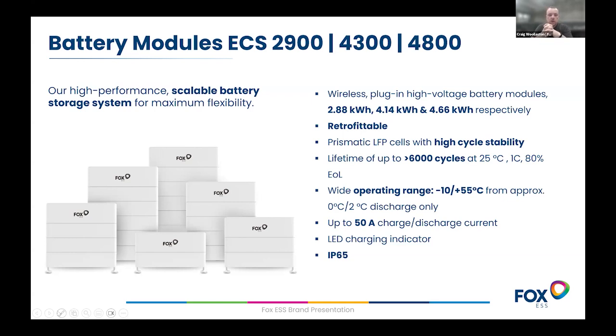The system comprises two elements. If you look at the image, you can see the battery on top with the logo - that's the master battery, a battery and BMS all in one. Beneath that you have slave units. There's no battery-to-battery cabling whatsoever. You build the stack, take the cables we provide between the master battery and inverter for your power and BMS connections, and then turn it on. That's your commissioning - there's nothing else beyond building the stack, plugging it in, and turning it on.